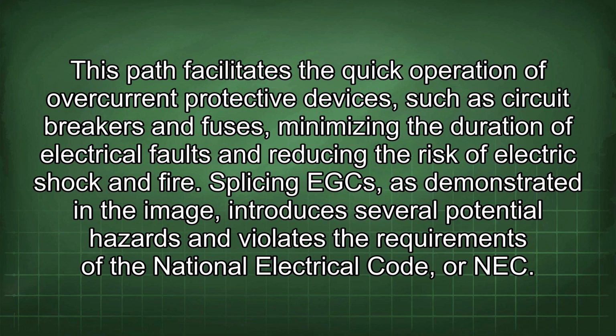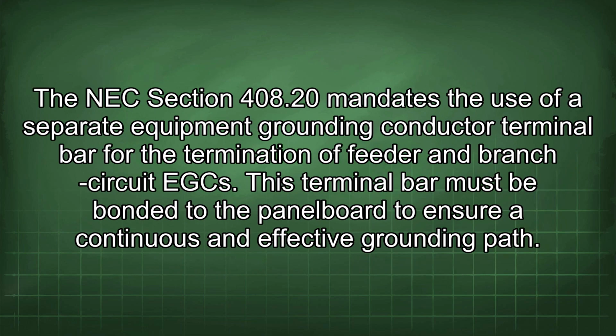Splicing EGC, as demonstrated in the image, introduces several potential hazards and violates the requirements of the National Electrical Code, or NEC. NEC Section 408.20 mandates the use of a separate equipment grounding conductor terminal bar for the termination of feeder and branch circuit EGC. This terminal bar must be bonded to the panel board to ensure a continuous and effective grounding path.